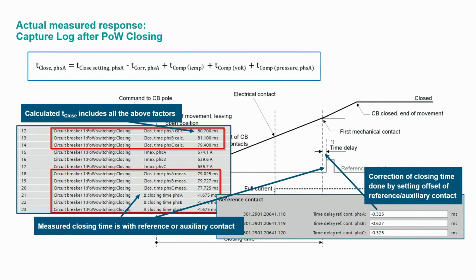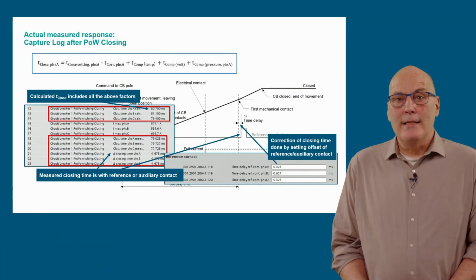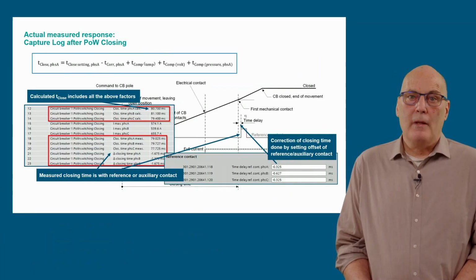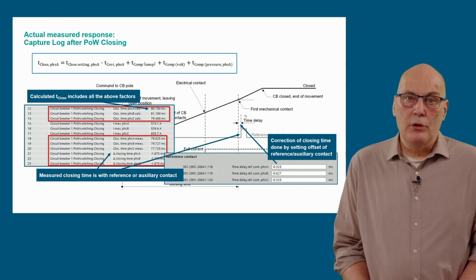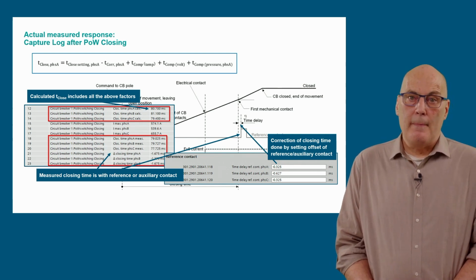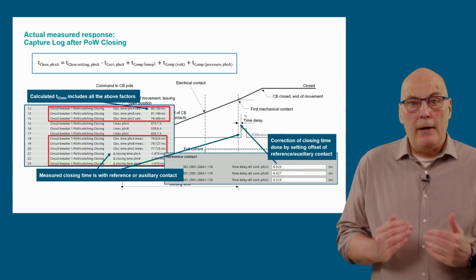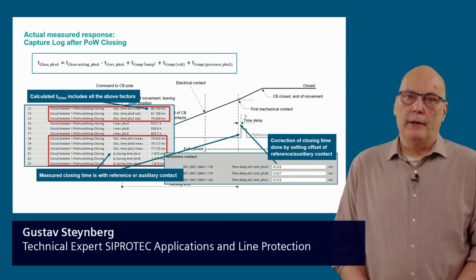After the point-on-wave close, read out the fault log as shown. The calculated close time for each phase is shown. This is the calculation as per the shown equation. For example, the calculated close time for phase A is 80.700 milliseconds. The next entry in the fault log that we check is the measured closing time. For example, 79.025 milliseconds for phase A. This is a time measured by the reference contact or auxiliary contact.